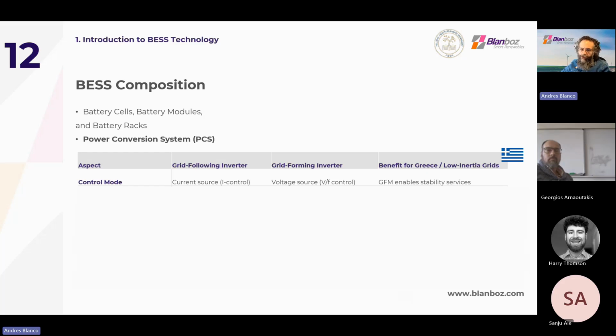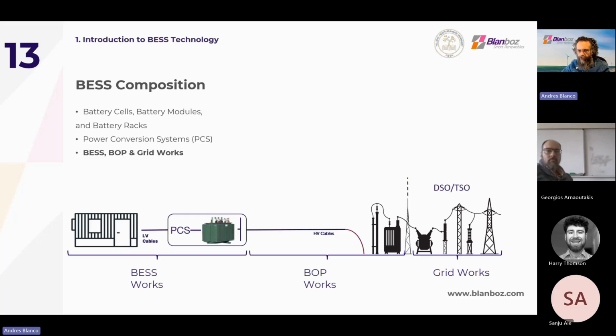Oscillation damping is very weak in follow inverters, excellent in forming, reducing low frequency oscillation that may occur due to a large plant tripping out or fluctuations from renewable energy generators. Response time for both is very fast since, as mentioned, PCSs and general converters are ideal and well placed for ancillary services and the stability market.